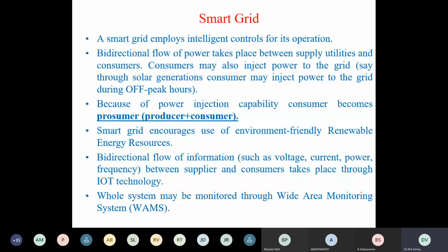And also there is a bidirectional flow of information, as well as a bidirectional flow of power. For example, voltage, current, power and frequency can be measured by smart meters, and this data can be transmitted through IoT technology and communication links to utilities. Measurements at different field locations are also performed through SCADA and WAMS, by RTUs, or by PMUs in the case of a wide area monitoring system. The measured quantities are transmitted to the control center, where there is application software, for example economic load dispatch and load frequency control.